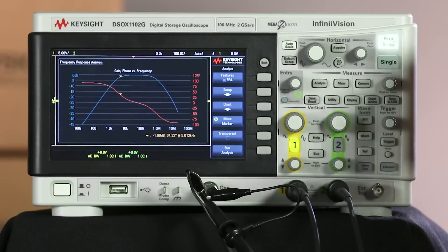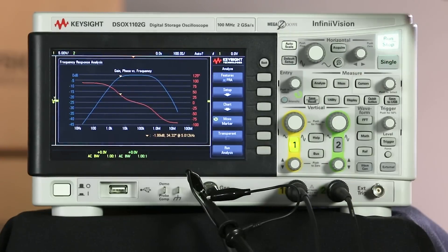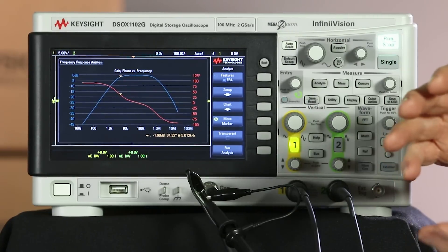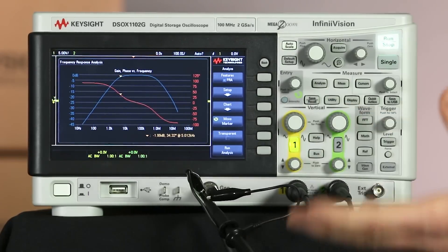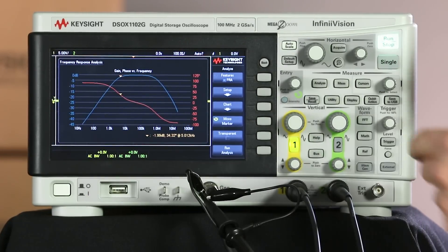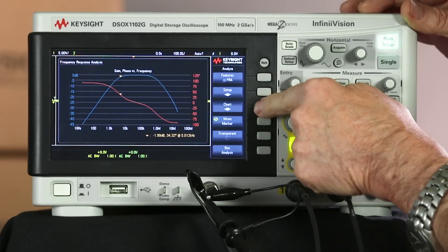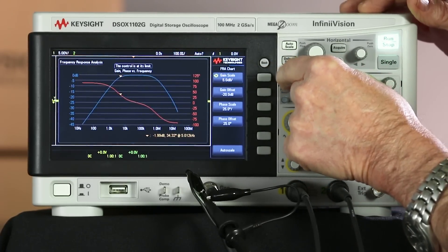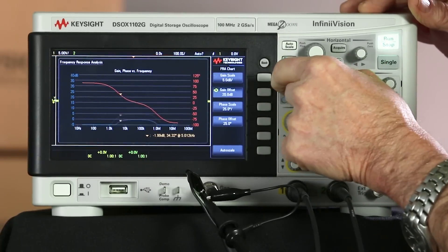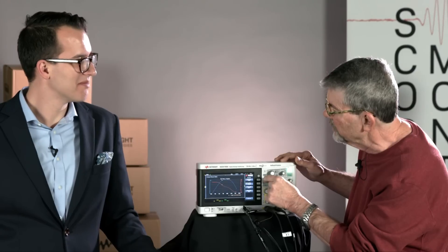It also auto scales the scaling of both the gain and phase plot at the completion of the test. So it's giving you optimum scaling, but you can manually change it. If I go into the chart, I could select gain scale and change that or gain offset. And then I could do the same thing with the phase plot as well.